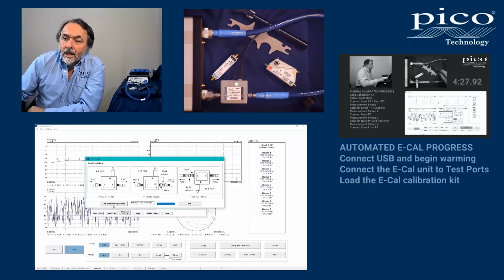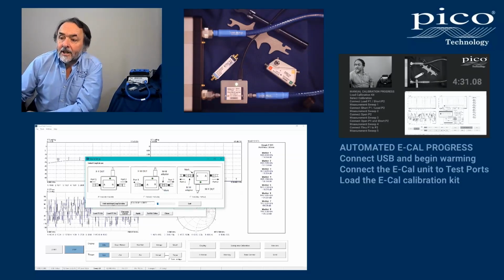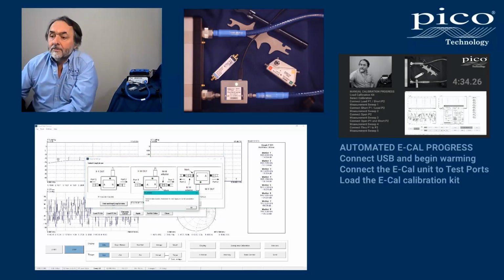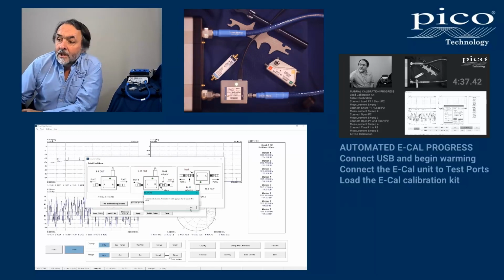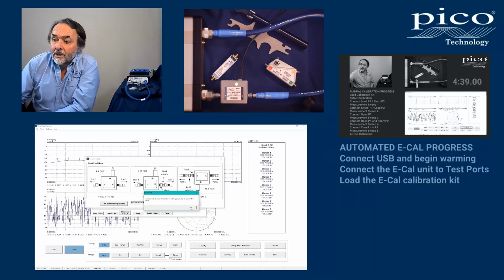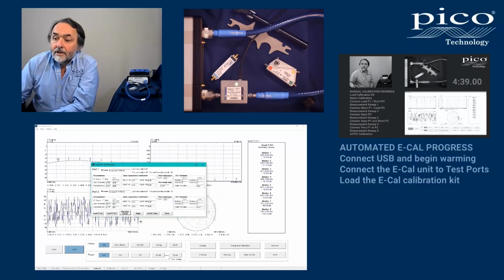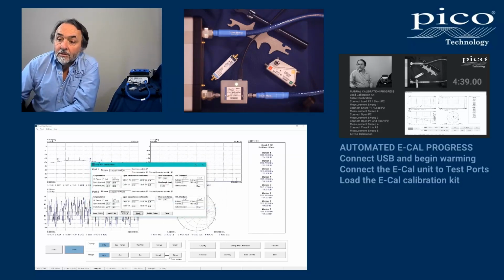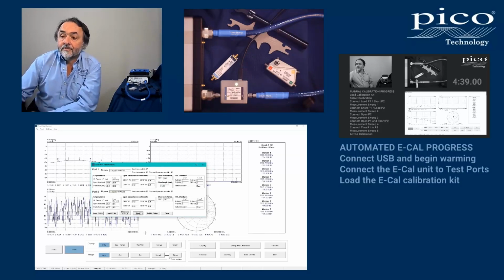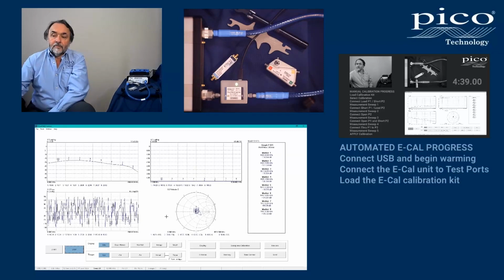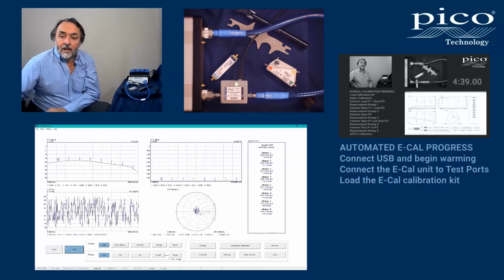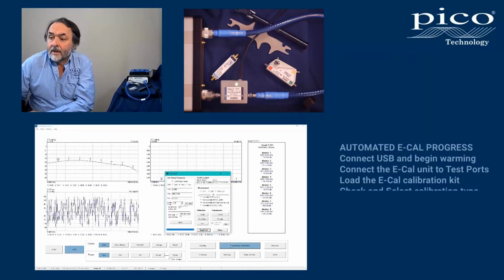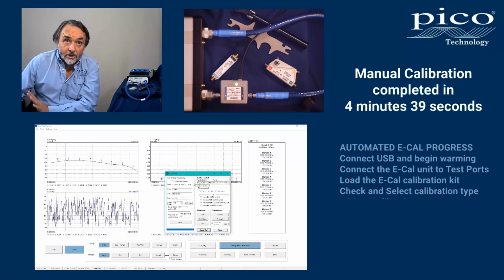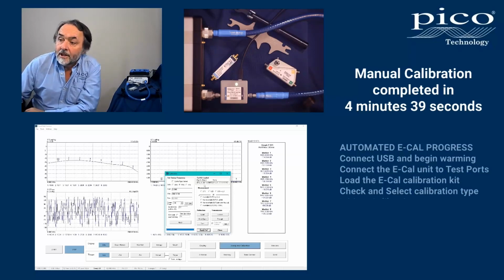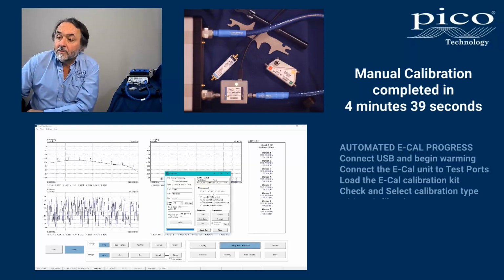So let's find and load the eCal data, and there you go, it's found this module. The eCal has been loaded. It's reminding me that I must still apply that when I leave this menu. Okay, exit, apply the eCal module to port 1 and port 2. Close. Okay, we are ready to perform our calibration. And you'll notice we always check that the modules are indeed loaded. Port A to port 1 and port B to port 2.